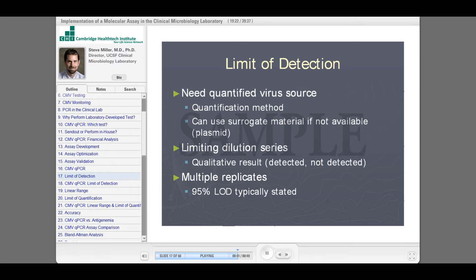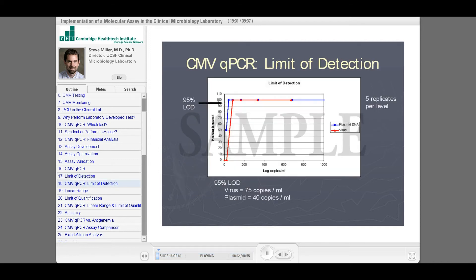So is this detected or not detected? You want to run multiple replicates of this. The standard definition for limit of detection is that you have detection of 95% of replicates at that level. So you may detect below the limit of detection, but you'll detect that less than 95% of the time if you run this over and over again.